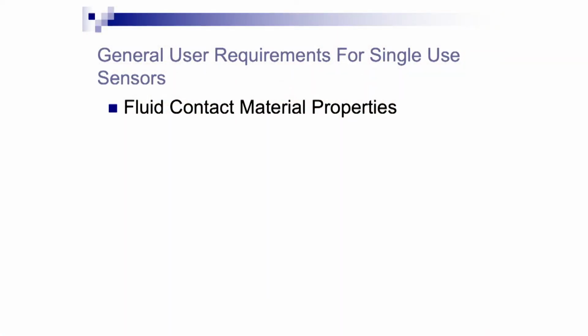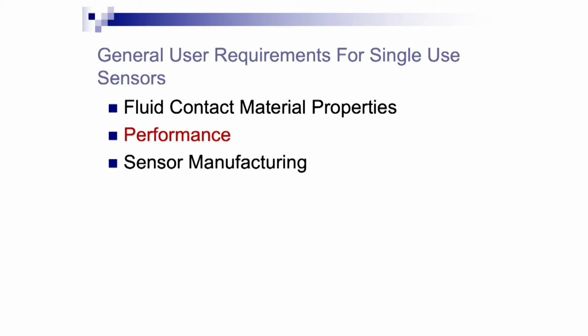In terms of the general user requirements, you want to look at fluid contact materials to make sure they meet the general standards of use, class 6, etc. You want to look at performance. This is what really separates a sensor from a piece of tubing or a fitting, is it must perform. The sensor manufacturing environment, just like other single-use components, it can introduce contaminants from the manufacturing, so it needs to be made in a controlled environment. The process compatibility, this is mainly related to solvents. Even though your process may not contain any harsh solvents, some of the preparation steps may, such as sodium hydroxide.